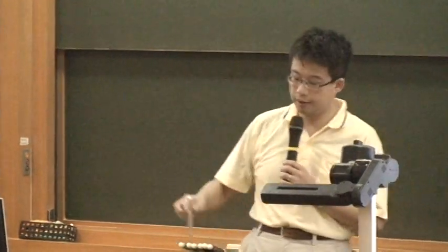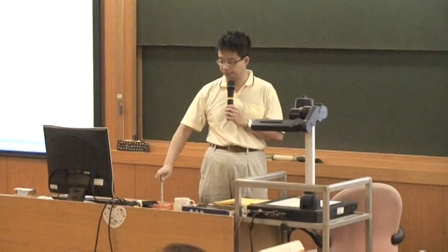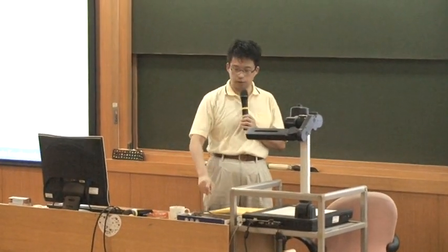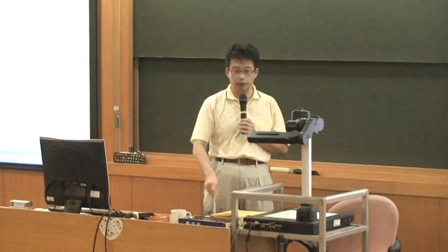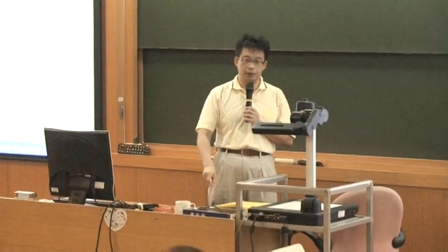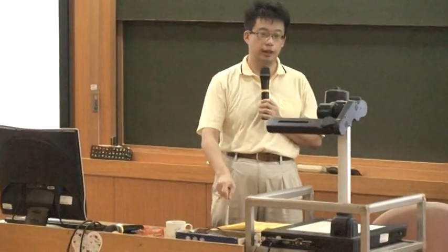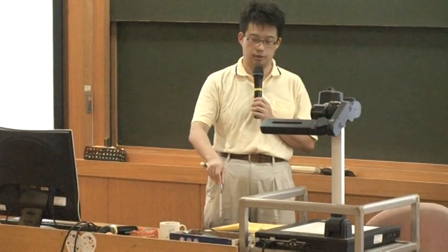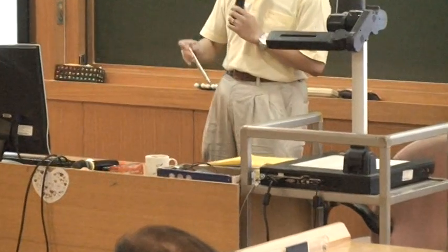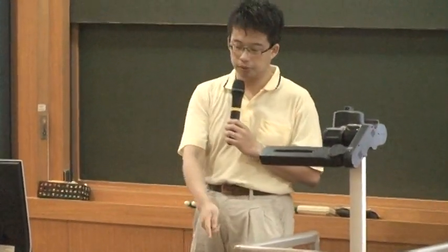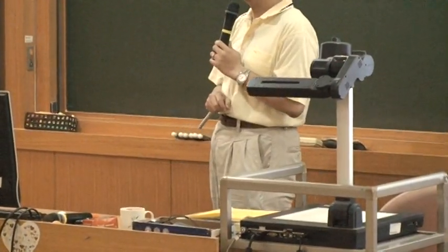Use this pointer as an example. If you scan the desk, you touch it, nothing happens because it's smooth to the pen and it does not need to move. But when this pen hits something, it needs to raise so that it can keep scanning. The distance it raises tells you the profile or the thickness of this box.